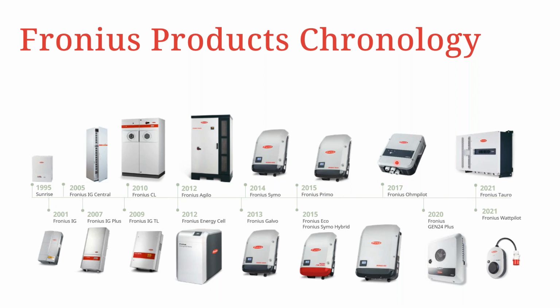We have other components or products that can be used to maximize self-consumption, such as the Fronius Ohmpilot, which was introduced in the year 2017. And this specifically is for hot water generation using excess PV energy that your system is generating. Then we have also the Fronius Gen 24 Plus, which is a hybrid inverter. So before that, the only other hybrid inverter was the Fronius Symo Hybrid, which was introduced in 2015. But this will eventually be replaced completely with the Gen 24 Plus. In addition to that, in 2021, we launched the Fronius Tauro, which is a higher power class for commercial systems. We will be giving a special mention of the Fronius Tauro today. And also in 2021, we introduced the Fronius Wattpilot, which is dedicated for EV application or for charging electric vehicles.